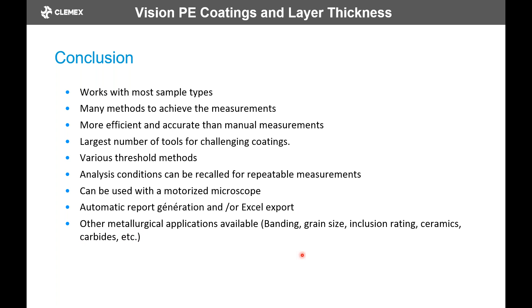One question is, can the multi-layer grab be used with a manual microscope? Yes, you can. Normally you use a motor to stack your images, but you can also use the focus. If you're working with a stereo, there's a little extra tool that you have to put in there, but you can use the multi-layer grab on a manual or motorized microscope. So you don't need a motorized stage. It's just better with a motorized stage. So a manual microscope can work with stacking.